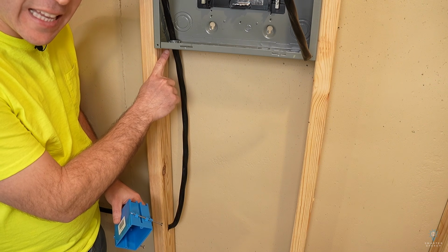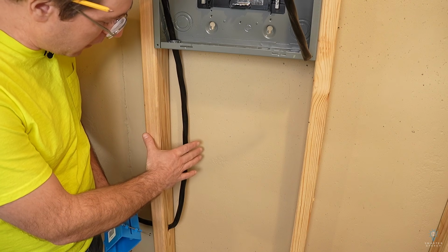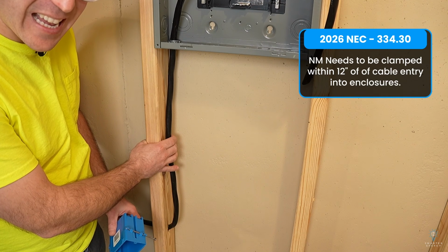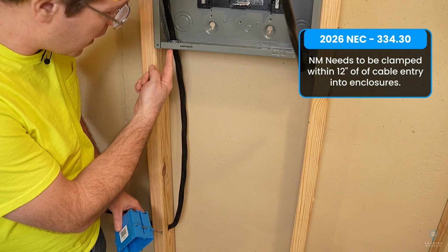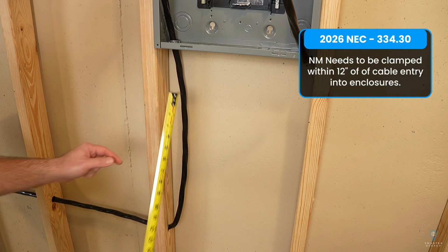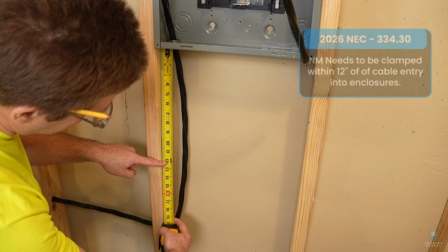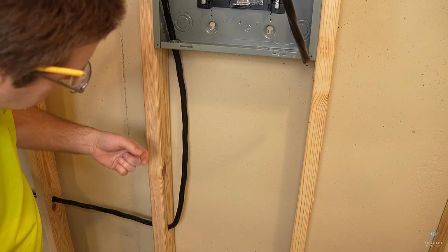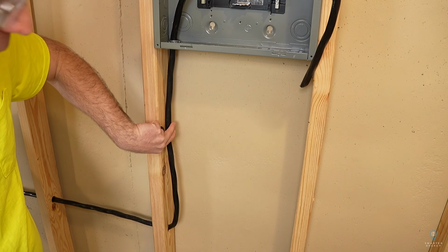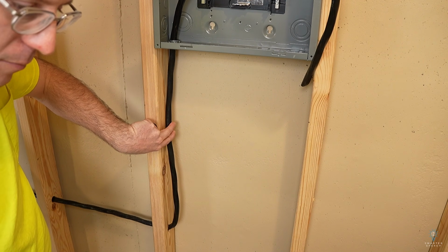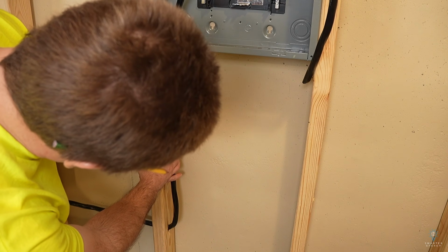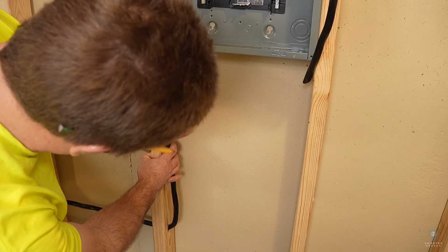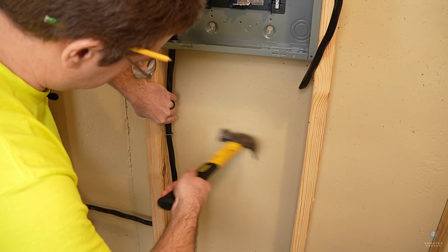Because we've installed a clamp on this panel, we can actually staple this NM within 12 inches of the electrical panel. So our staple needs to be between here and here. I'm just gonna grab it arbitrarily right here and we're gonna staple it right there. So I'm gonna hold the wire roughly in the middle of the stud and we can tack it in.